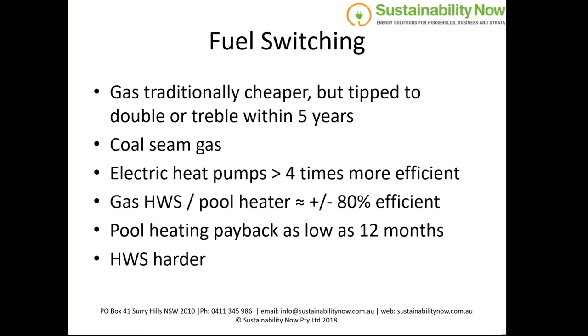So the big thing I'm seeing is moving away from gas pool heating to electric heat pumps. Those are more than four times more thermally efficient than a gas heater, sometimes up to six times more efficient in lab conditions. Even though gas is still slightly cheaper per unit of energy, it's still much cheaper to run an electric heat pump than a gas heater. Your gas heater, if you're lucky, might be 80% efficient, whereas an electric heat pump could be 400% or 500% efficient.